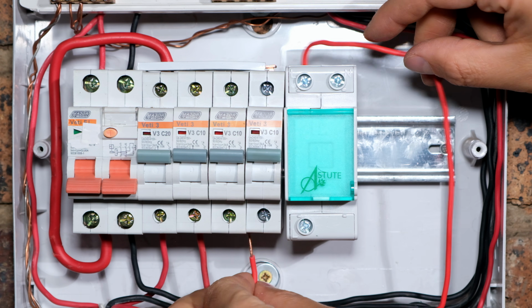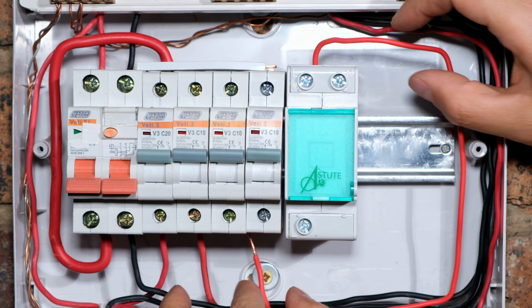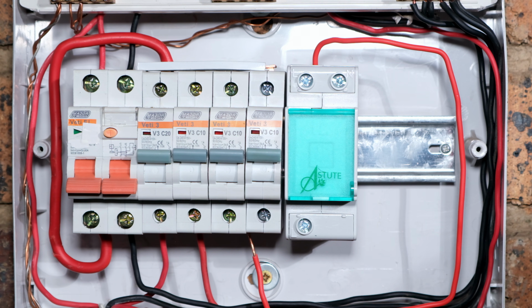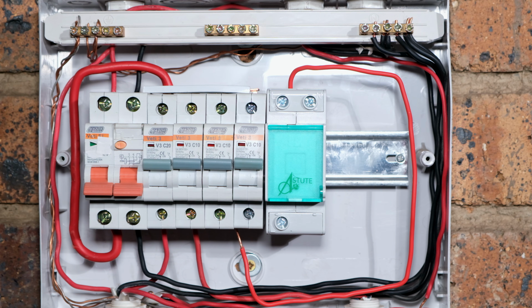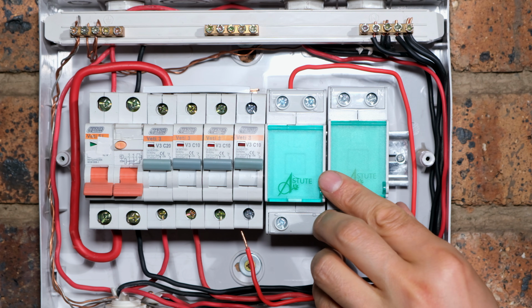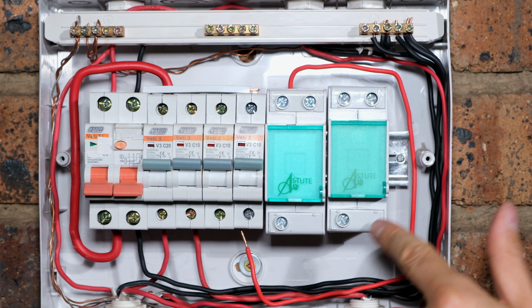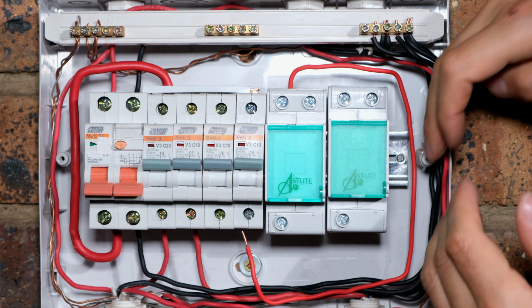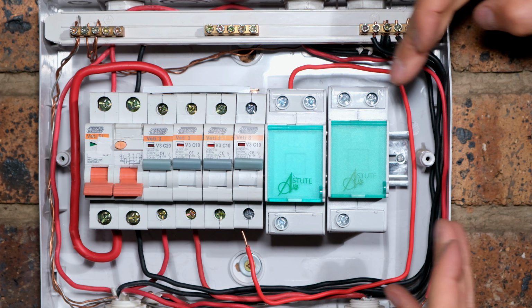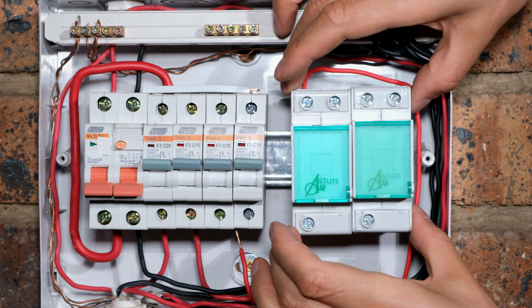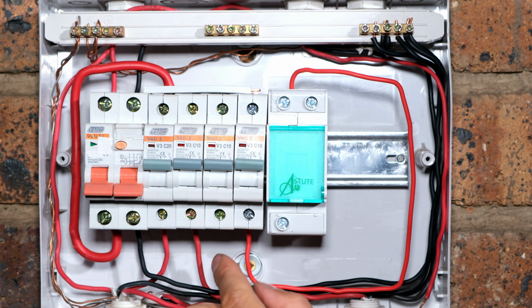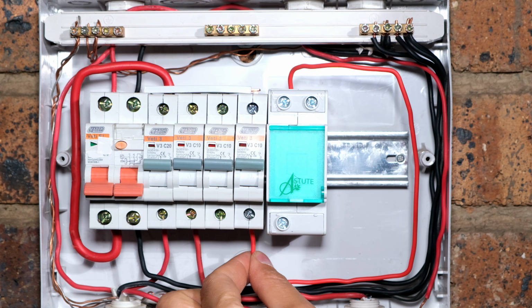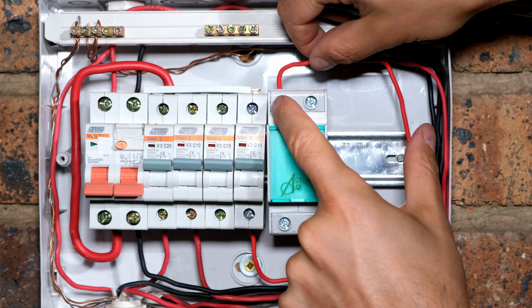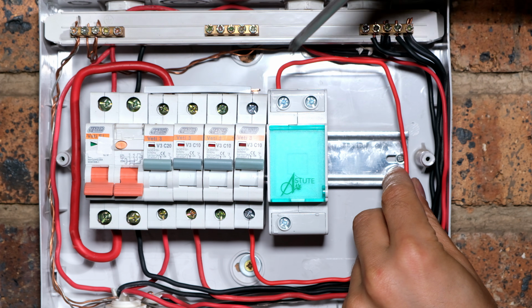Now you might be wondering, why did I make it so wide? The reason is that I want to have the scope to add another timer if I want. In future, if I want to add another timer, then the wire that I've just put here is not in the way. So I make sure that I wire it towards the edges, also giving me the opportunity to add circuit breakers and expand if I want. I've opened the screw for the circuit breaker and I've tightened the wire inside there. The wire is then going to the live terminal of the timer.